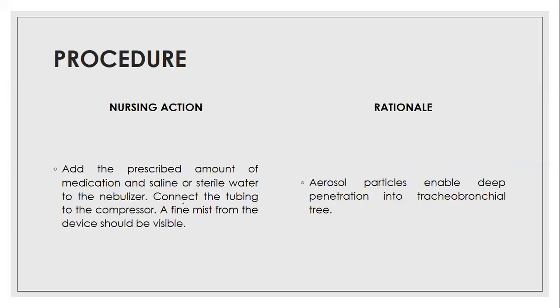Then, add the prescribed amount of medication — it may be Duolin or Budecort, but follow the doctor's order. Add the medication along with saline or sterile water to the nebulizer cup. We can use either saline or sterile water with the medication. Sometimes we can provide medication alone. Then connect with tubing to the compressor — a fine mist from the device should be visible.